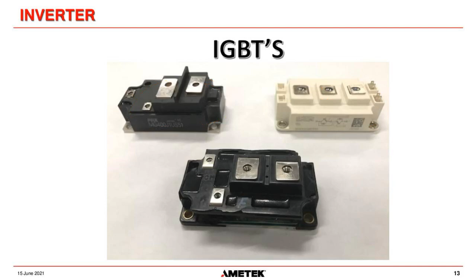I always like to show this picture, because if you see an IGBT like this, then something's gone wrong. You've let the magic smoke out. This is what a damaged IGBT can look like. The problem with IGBTs is they are very, very current sensitive, very sensitive to high current, and there is no fuse on this planet that can protect an IGBT from destroying itself in a high current situation. It has to be done electronically through the control circuits. So if there's a problem with the IGBTs or the control circuit, and two IGBTs switch on at the same time causing a direct short, this picture shows what it will probably look like afterward. So try not to do that.